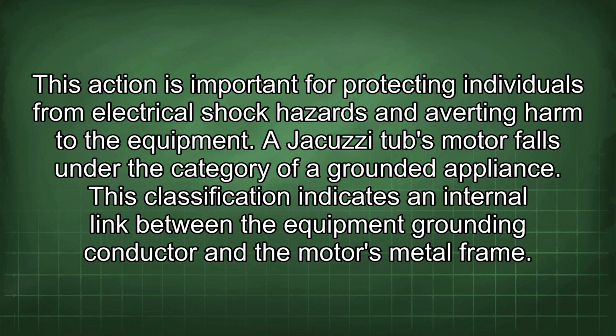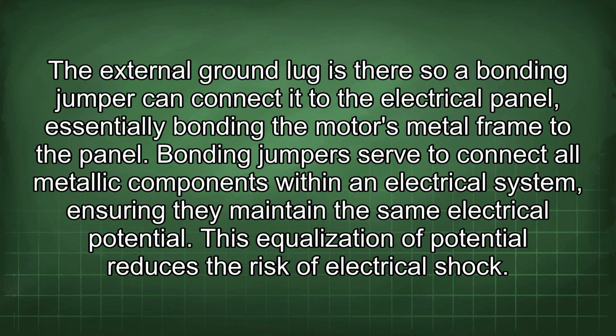A Jacuzzi tub's motor falls under the category of a grounded appliance. This classification indicates an internal link between the equipment grounding conductor and the motor's metal frame. The external ground lug is there so a bonding jumper can connect it to the electrical panel, essentially bonding the motor's metal frame to the panel.